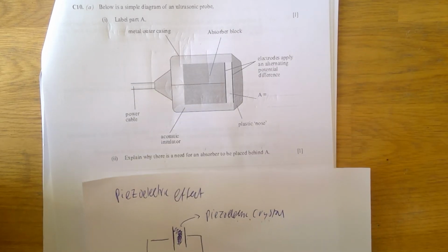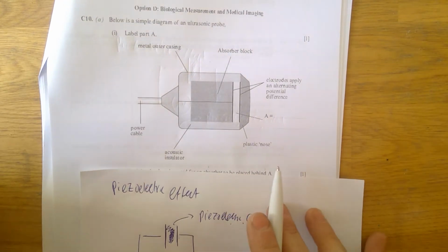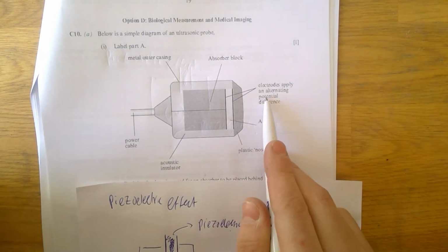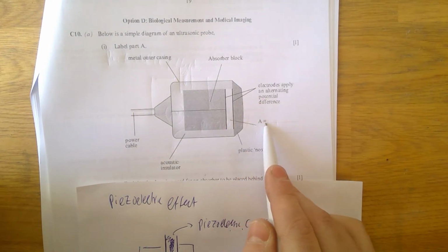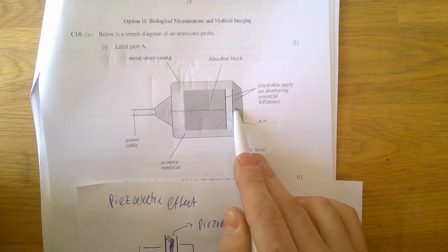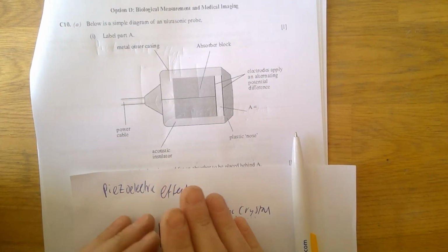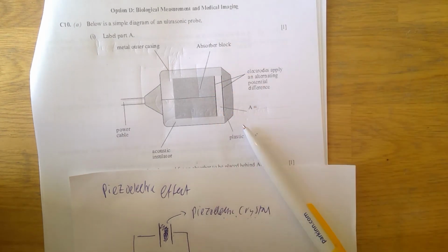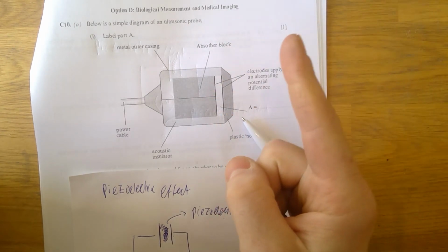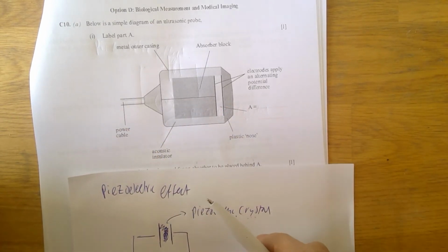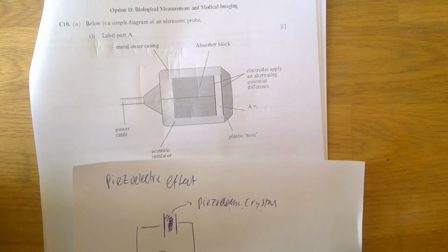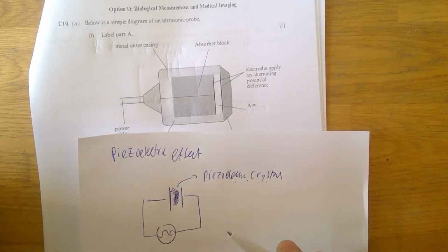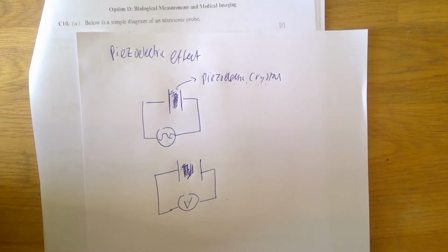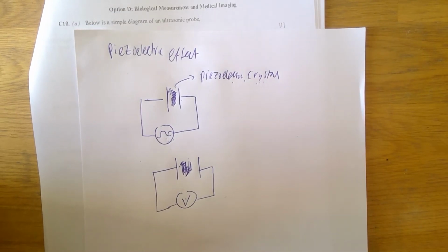So, if we look at this probe, what we've got here is something like this. You've got the electrode supplying alternating potential difference to the piezoelectric crystal between those plates. And you do that as a pulse. So you send out a pulse of ultrasound. Off it goes. That will bounce off something, come back, make this vibrate to produce the alternating voltage that you record. So it's a bit like sonar. You send out pulses, boop, ping, comes back, you detect it. It's a bit like echolocation. Okay, so that's how you produce and detect ultrasound.